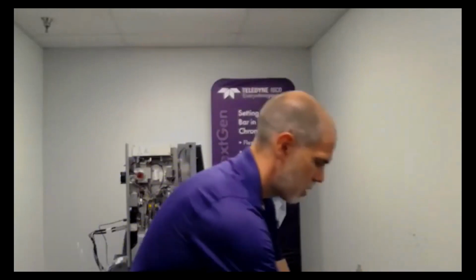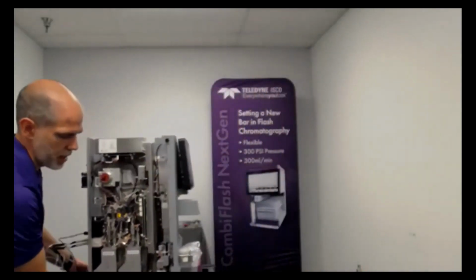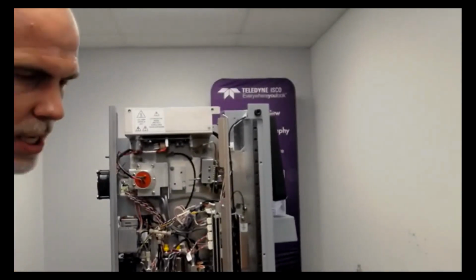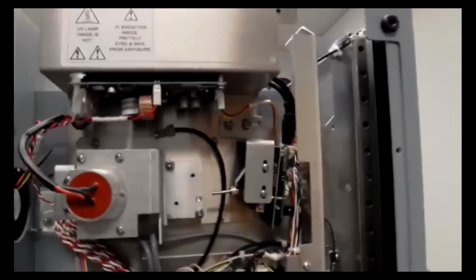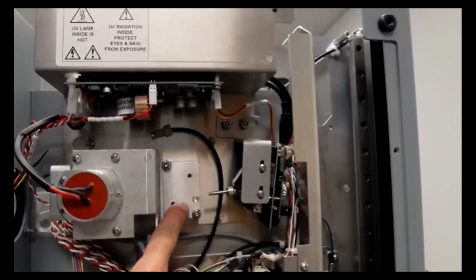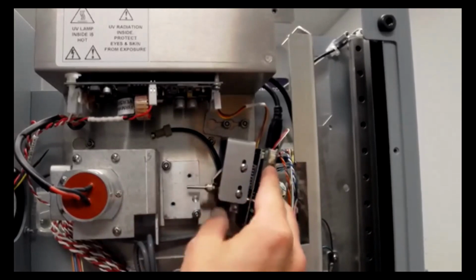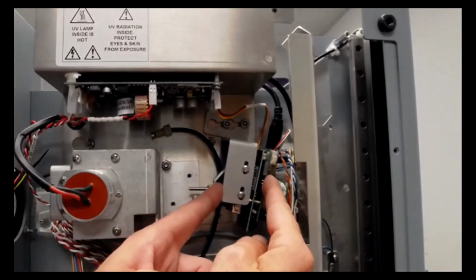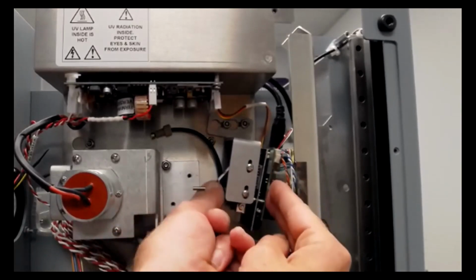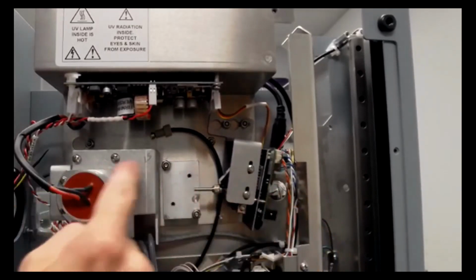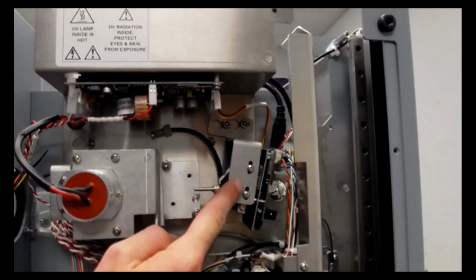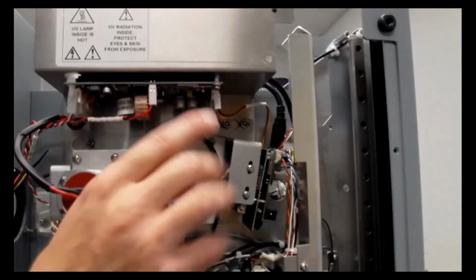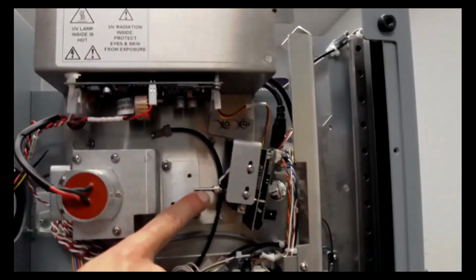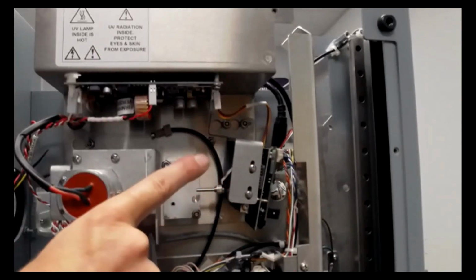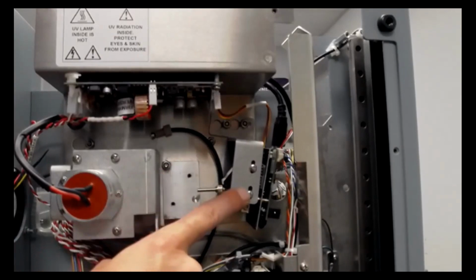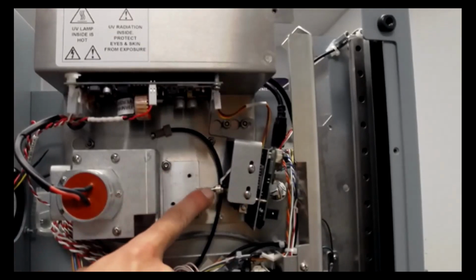And a good troubleshooting thing is when you have bad light energy, the first thing that I would suggest you do is just take a light energy reading with the full thing assembled. And then you want to start taking things out. So here, for example, we've taken the flow cell out. So I would move the detector back and I would do a light energy reading through just the rod to the detector. If I'm still not getting good light energy here, we remove this rod. It's just a knurled nut. You remove it by hand and you shine light directly onto the detector. Now, if this is shining directly on the detector, it should peg. It should be the highest possible detector reading you can get. If you're not getting that, then you've got a bad detector. If you've got pegged detection of light energy from just the light shining on it, but not with the fiber optic installed, then your fiber optic is bad, okay?